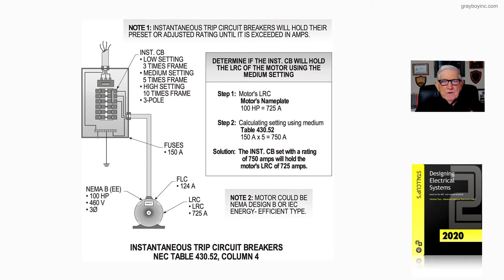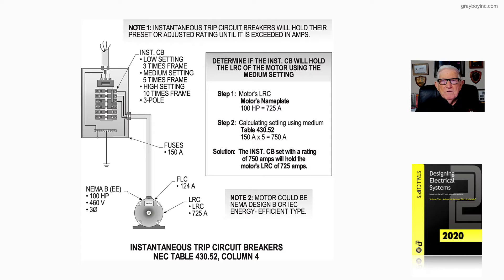This illustration deals with instantaneous trip circuit breakers. In the old days they came available in fixed settings: the low setting was three times the frame, so for a 150-amp frame that would be 450 amps. The medium setting was five times the frame — five times 150 equals 750 amps. The highest fixed setting was ten times the frame, so ten times 150.